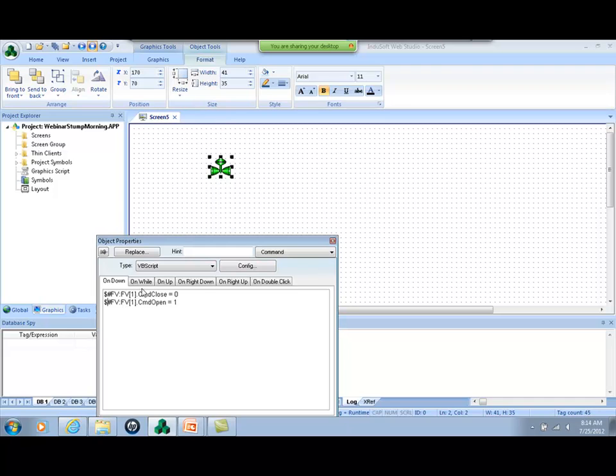And it's very nice when I use classes. I can assign the same alias to different members of the same class. So during the runtime, I do not have to customize each member anymore, just the main tag. It will become much clearer in a few seconds here. So I'm gonna use the same alias everywhere here. The alias fv, which is the name of my custom property for this linked symbol.